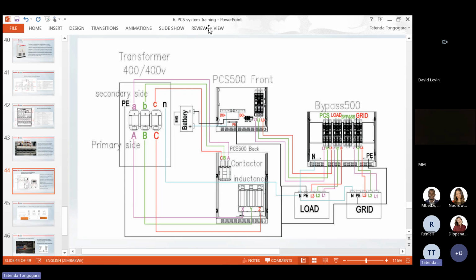So always take note of these connections, because if you make a wrong connection, I've seen problems where now you have to buy new cables, and these cables are very expensive because the 95, 150 square millimeter cable is very expensive. So before you cut your cables, before you do anything, please seek clarity if you are not sure, because this mistake is very costly. So just seek clarity if you are doing this connection. We help you with this connection. We do online support, which is free of charge.